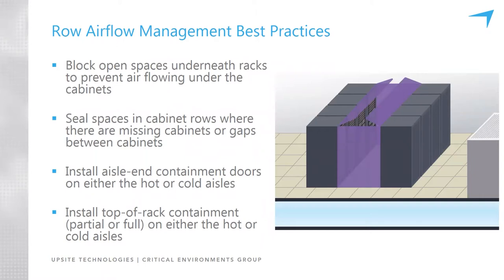These four bullets represent the key best practices for row or aisle-level airflow management. We'll get into much greater detail on each of these on subsequent slides, but here's a quick overview. The first is blocking off open spaces under the racks. Cabinets are often delivered with casters and levelers to aid with initial deployment, which by default creates a gap between the floor and the bottom of the rack — and blocking this gap is what we're referring to here.